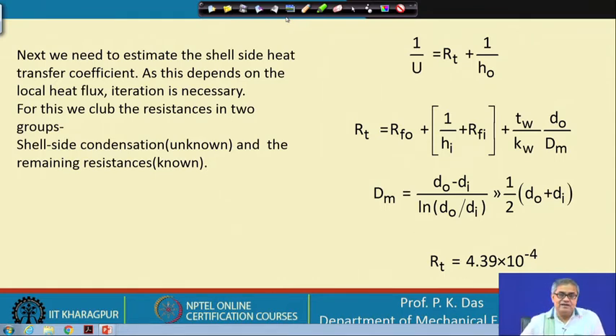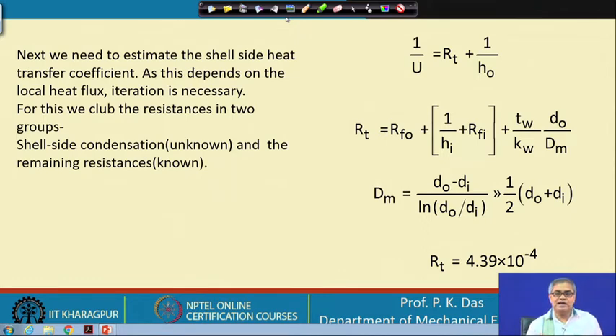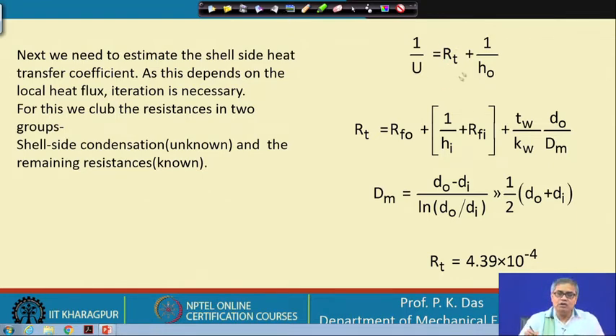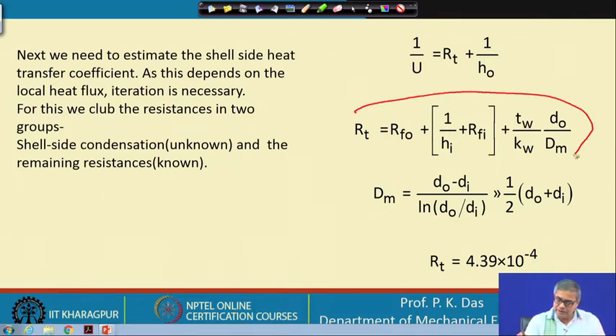Next, we need to estimate the shell-side heat transfer coefficient, that is the tube-outside convective heat transfer coefficient due to condensation. Since this depends on the local heat flux, iteration is necessary. For this, we club the resistances in two groups: the shell-side condensation resistance, which is unknown and a function of delta T_w, and the remaining resistances, which are known.